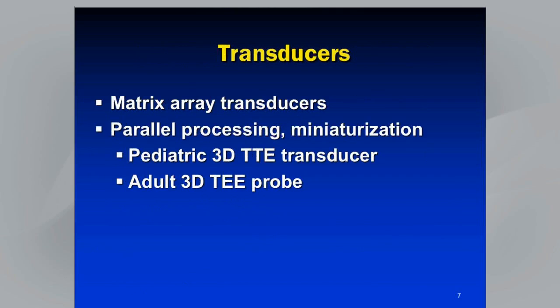One of the biggest differences with 3D echo has to do with the transducers. These are matrix array transducers that are typically cut from single crystal, resulting in over 3,000 elements per transducer head, with connections to each of those elements that are less than the thickness of a single human hair. In addition to the advances in transducers have come advances in parallel processing as well as progressive miniaturization. Miniaturization in particular has led to the development of the pediatric 3D transthoracic echo transducer and the adult 3D transesophageal echo probe, both of which are now almost a decade old, actually.